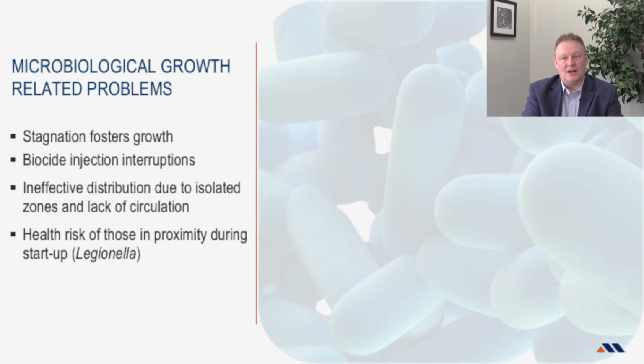By interrupting the biocide injections, health risks may also arise. Stagnation fosters biological growth, so even partial stoppages become an important risk. The stagnant areas can rapidly become areas of bacterial growth, and we know that bacterial and Legionella proliferation creates a high risk for those in proximity during startup.